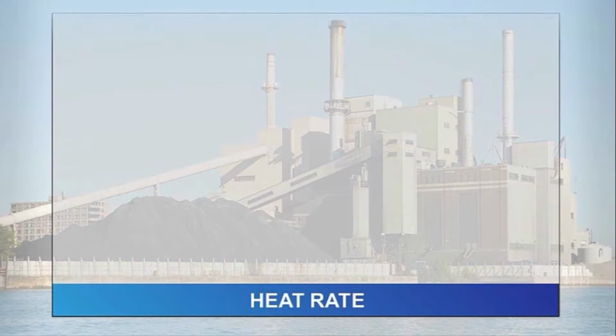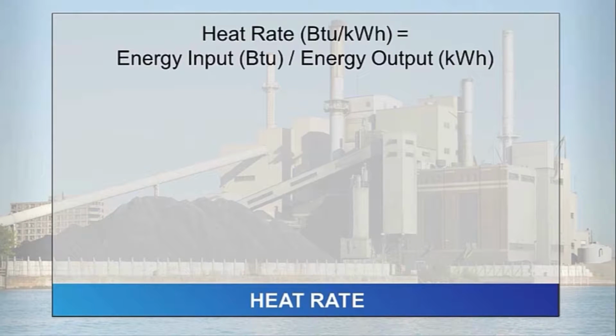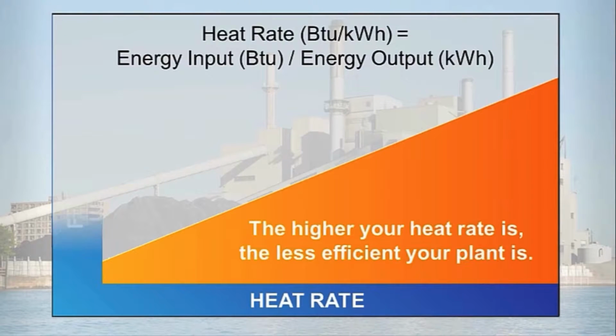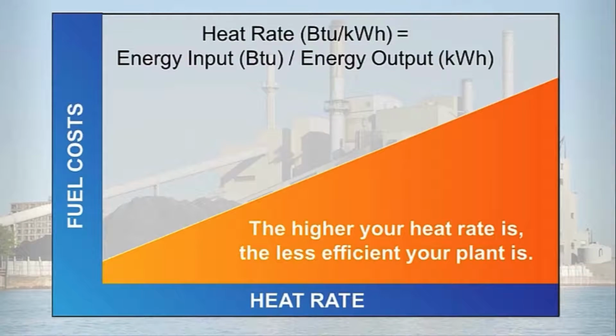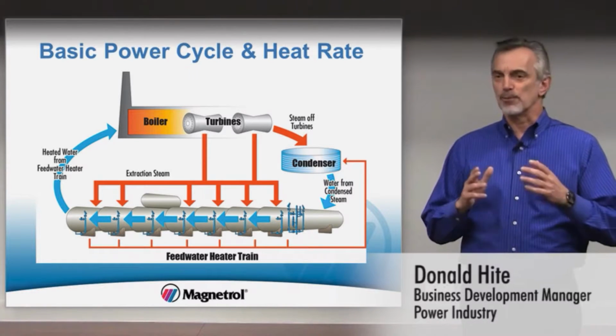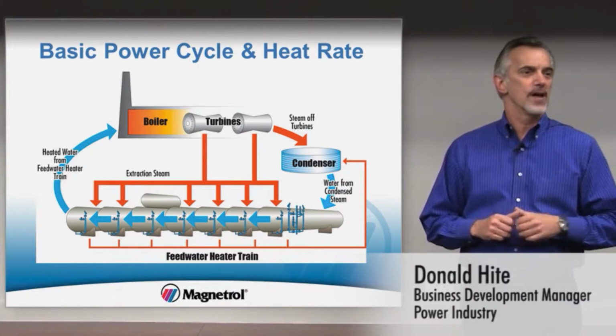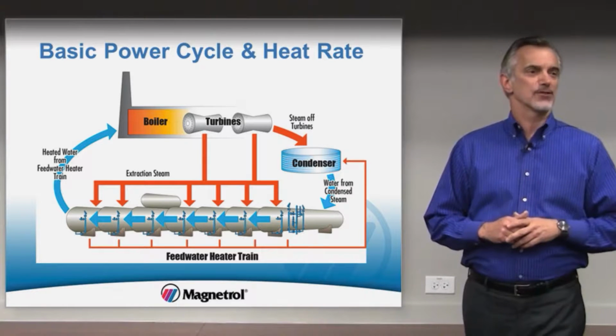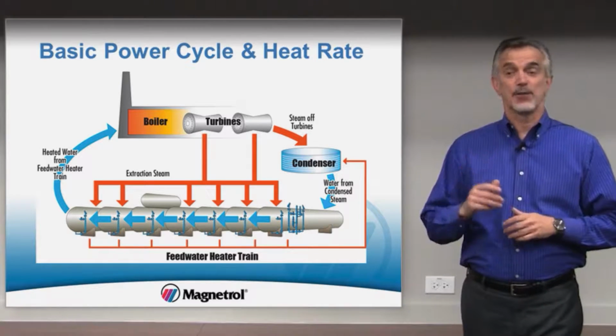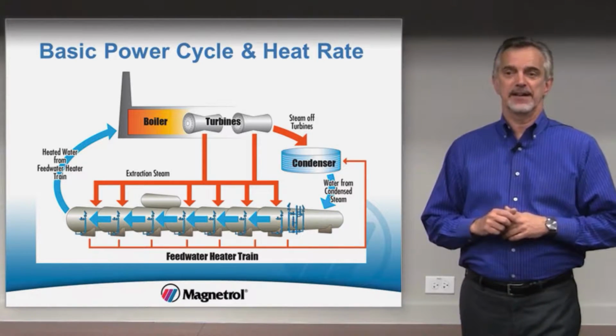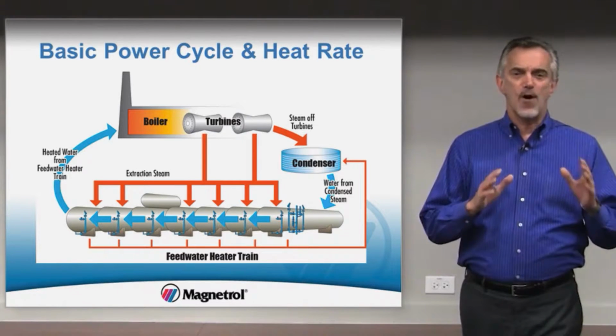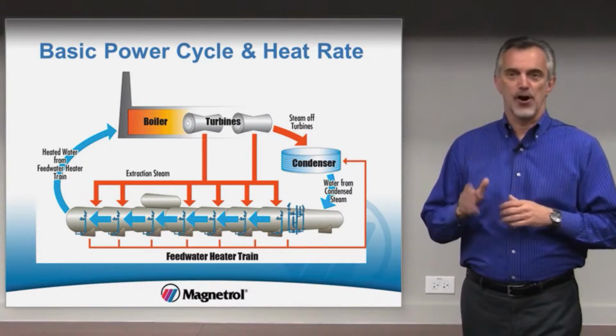Heat rate is a measure of how efficiently a power plant uses heat energy. You can measure heat rate by the number of BTUs your plant requires to generate a kilowatt hour of energy. As your heat rate goes up, so do your fuel costs. Although a reduction in fuel costs through improved feedwater heater level control has the most significant impact on a company's bottom line and their ability to compete in unregulated energy markets, the benefits go far beyond consumption and cost.